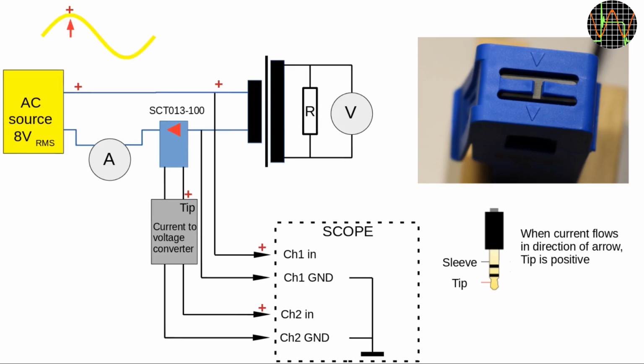That's not really necessary, but the waveform on an unloaded transformer are quite strange, and I wanted a more realistic picture. To verify the correct phase relation between channel 1 and channel 2, it is useful to imagine the AC wave frozen at the positive peak. In this case, the current flows from the source through the primary winding, through the current transformer, in the direction of the arrow, through the multimeter and back to the source.